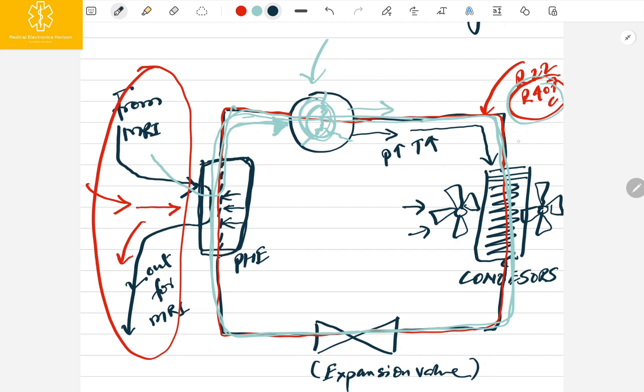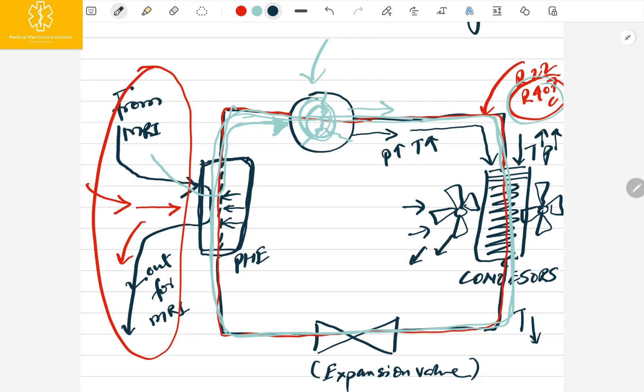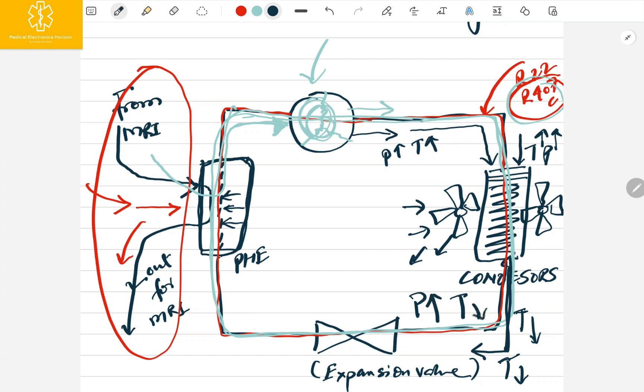From the compressor, the gas goes to the condenser. The fans are moving in the condenser part. This refrigerant gas enters the condenser with high temperature and high pressure. When the gas enters, it condenses — the fans take the heat out into the atmosphere. The gas coming out from the condenser has a lower temperature, though the pressure is still high.